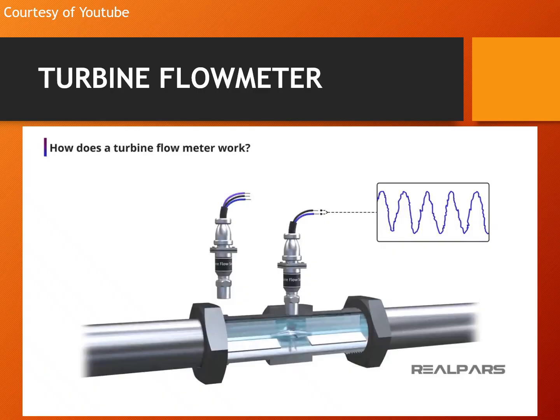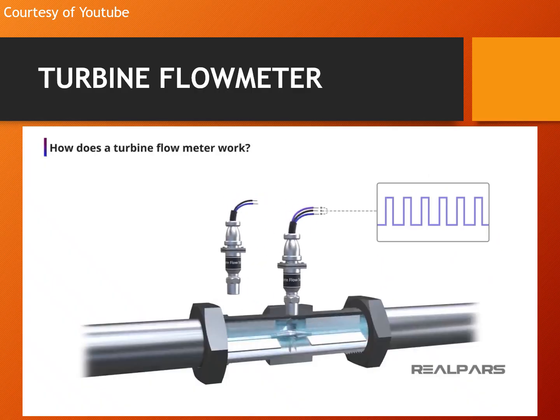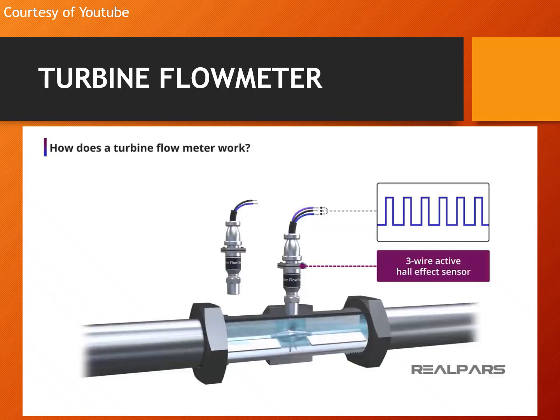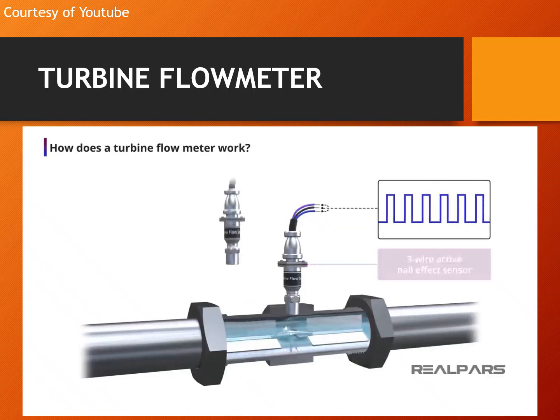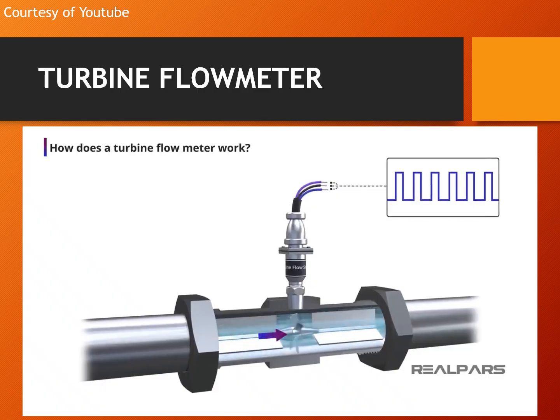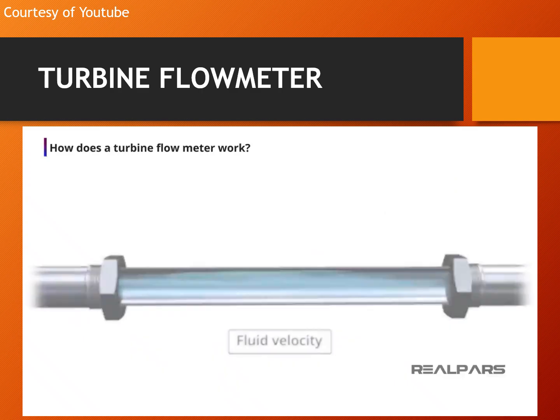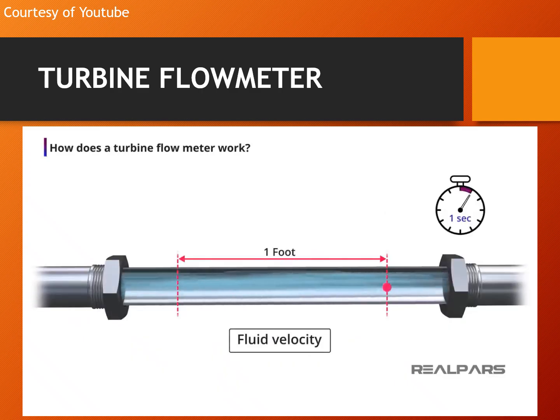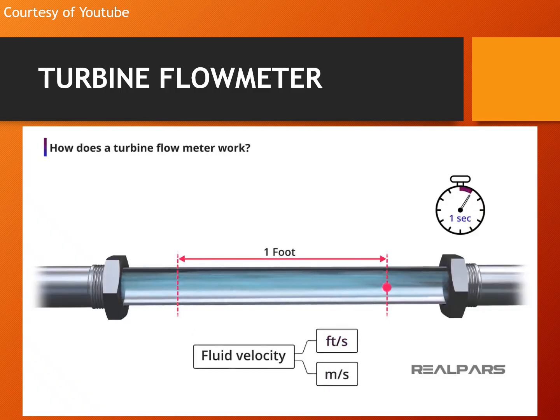The electrical pickup sensing device could be a simple two-wire passive magnetic pickup producing an AC type output. The electrical pickup sensing device could be a three-wire active device, such as a Hall effect sensor, that produces cleaner and more uniform square wave pulses. As we said earlier, the turbine rotor will turn at a different speed depending upon the fluid flow velocity. Fluid velocity is a measurement of the distance a particle of a substance traveled per unit of time. Typical velocity units are feet per second or meters per second.